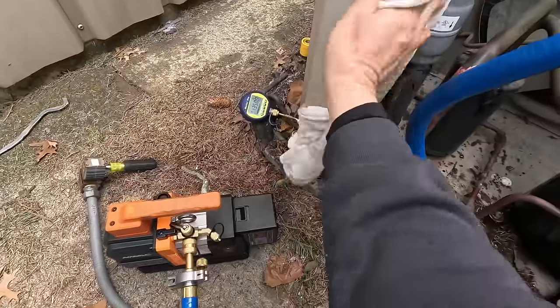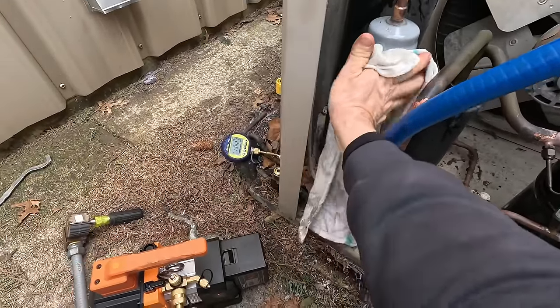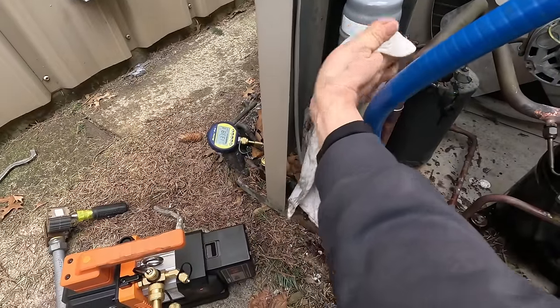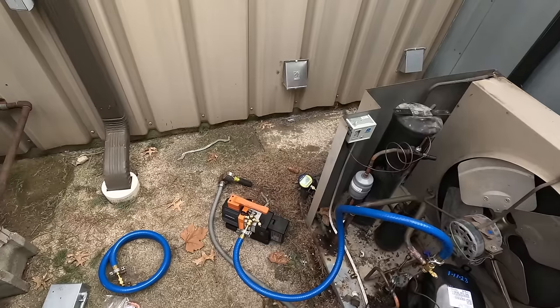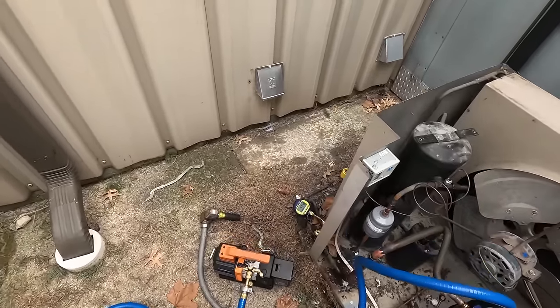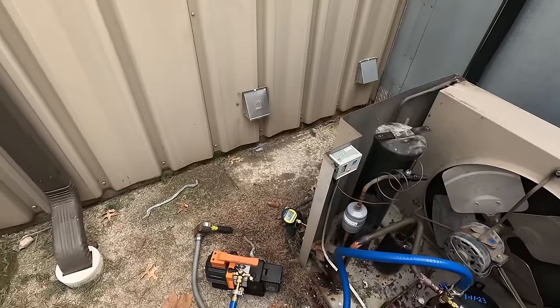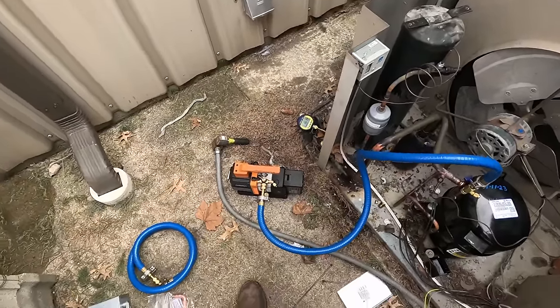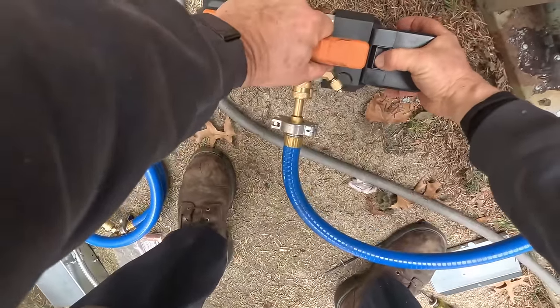That's the problem with these dryers — got a little bit of something on it and it wipes your labeling right off. You need to go back to printing it on. I'm starting to go bad — that battery did not last very long. We're at 974 microns and I only got about 34 minutes total run time out of it. NAVAC, I'd really like to have another battery. So we're going to go ahead and kill that and yank this battery.